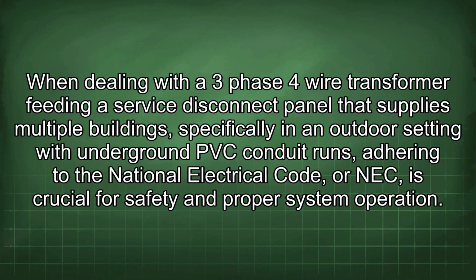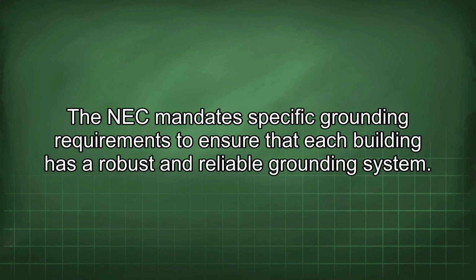When dealing with a three-phase 4-wire transformer feeding a service disconnect panel that supplies multiple buildings, specifically in an outdoor setting with underground PVC conduit runs, adhering to the National Electrical Code, or NEC, is crucial for safety and proper system operation. The NEC mandates specific grounding requirements to ensure that each building has a robust and reliable grounding system.